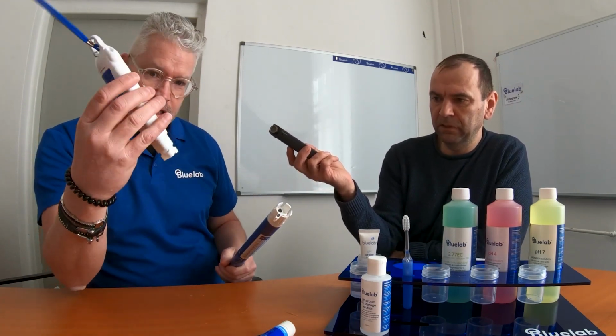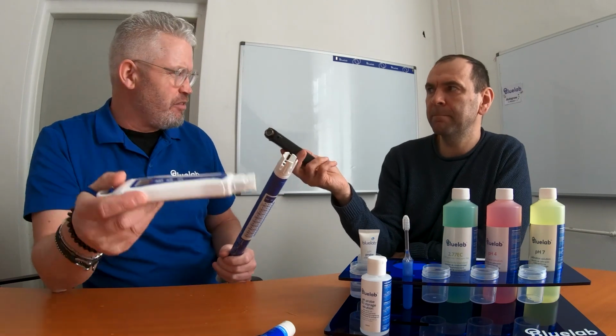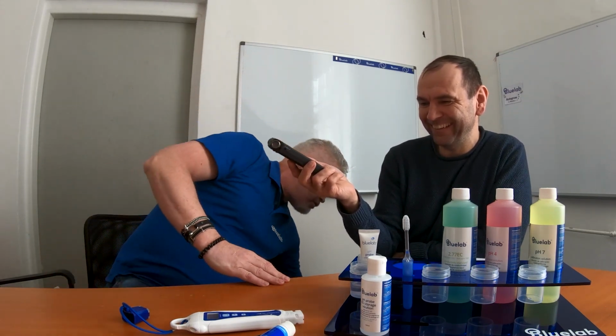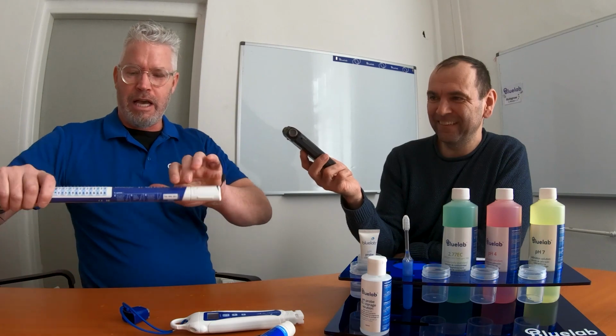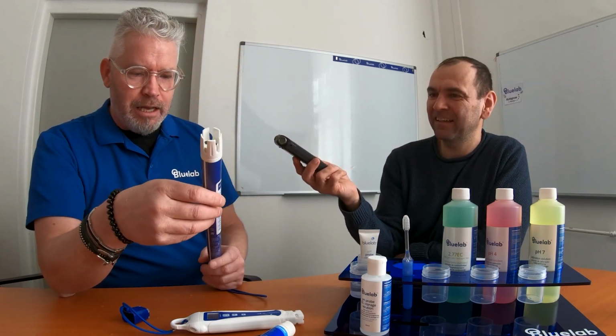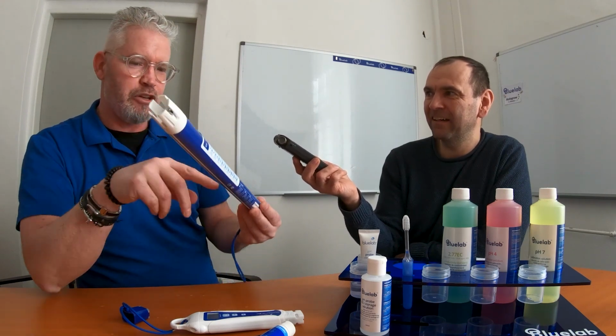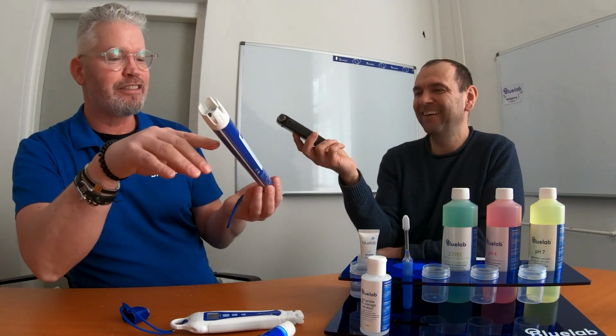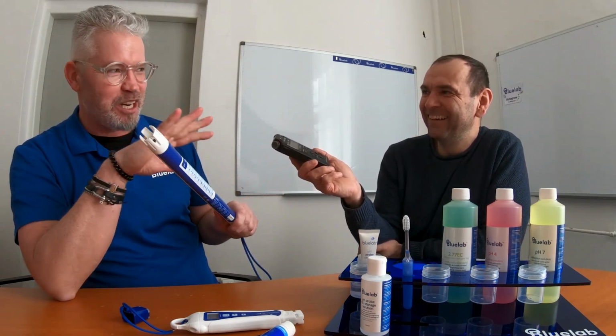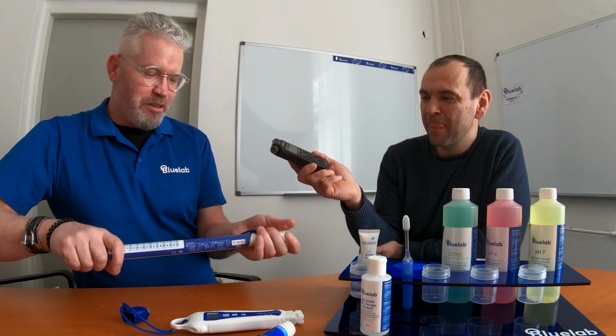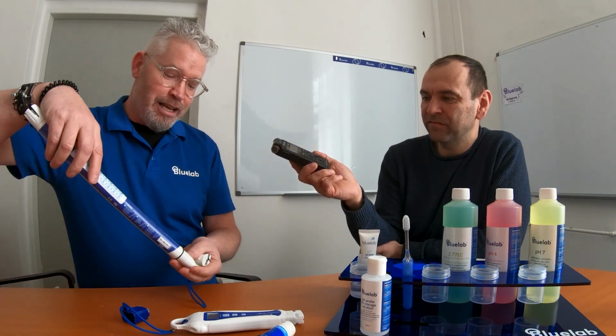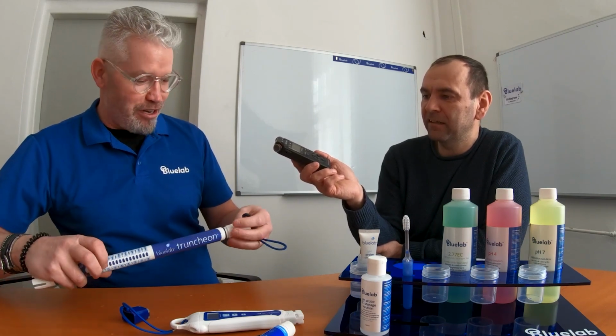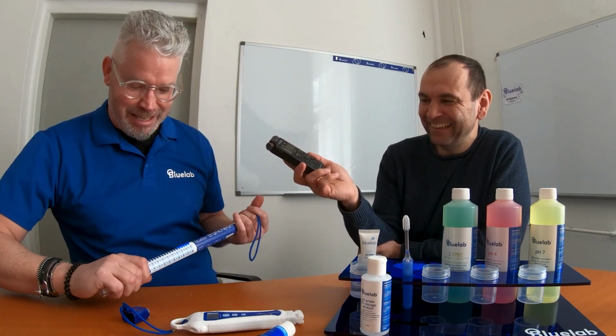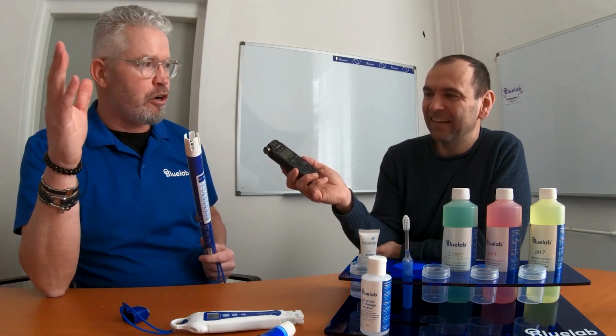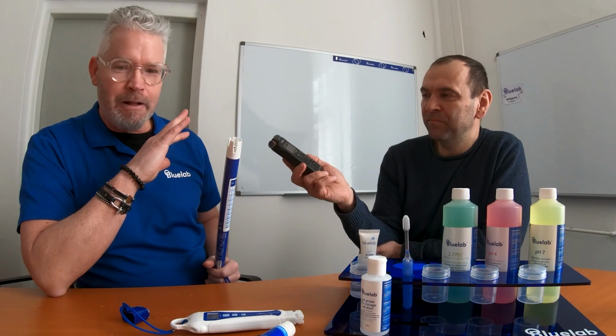Good. This one has glass, so you don't want to drop it, because then the glass breaks. But this one, it's just a sensor. I can just drop it on the floor, so it's very robust. I have seen one lying on a heating system, and it got hot and melted, and it was curved like a banana, but it was still working. So as long as you use the same batteries and you put them in the proper direction, it keeps on working. So EC requires only cleaning, nothing else.